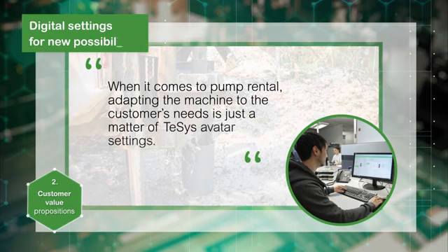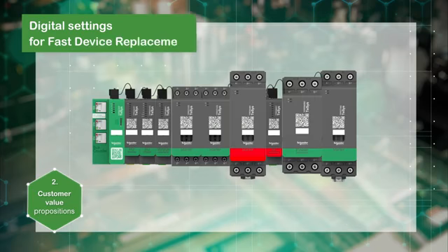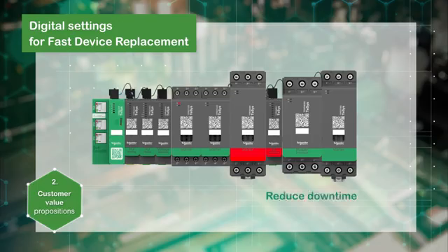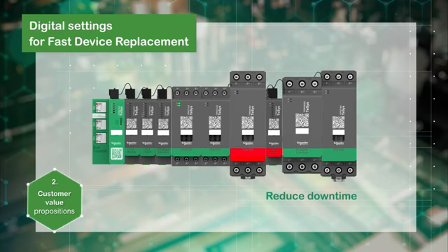Fast device replacement enables quick replacement in case of failure. Just remove the device and replace it to reduce downtime. The bus coupler automatically updates the new device with the relevant configuration. The same procedure applies to the bus coupler. Insert the SD card to reload the saved configuration or use the FDR through the PLC.